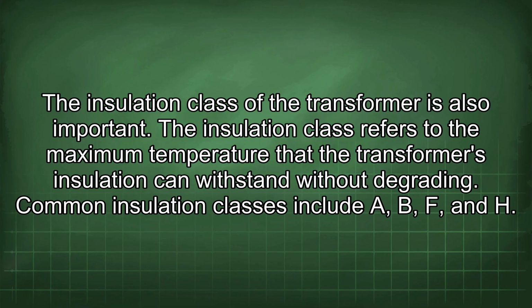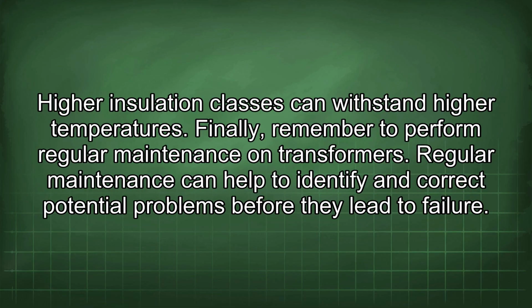The insulation class of the transformer is also important. The insulation class refers to the maximum temperature that the transformer's insulation can withstand without degrading. Common insulation classes include A, B, F, and H. Higher insulation classes can withstand higher temperatures.